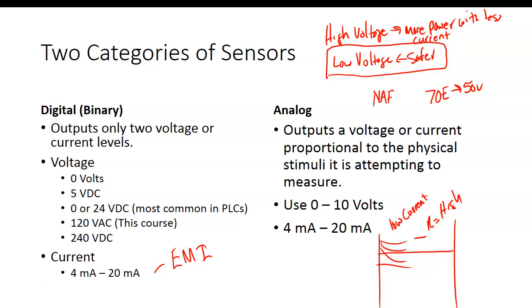You're still going to run into some current interference, and if I run voltage to these sensors I have to shield them and add more protection. So with current, I'd use 4 milliamps to represent off and 20 milliamps to represent on. We have to process that, and relays don't have that capability, so it adds expense, but in return I don't have to worry about EMI.